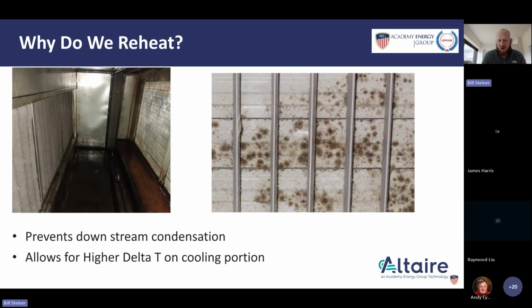Typically, the first thing we see after a mixed air mixing chamber, shelf mixing, whatever you're doing there to mix your air, are the filters. Those are probably the worst thing that could have fully moisture laden air to hit them, right? Because they're a breeding ground for mold and bacteria, and we have a pressure differential there. So it will wring the moisture out.